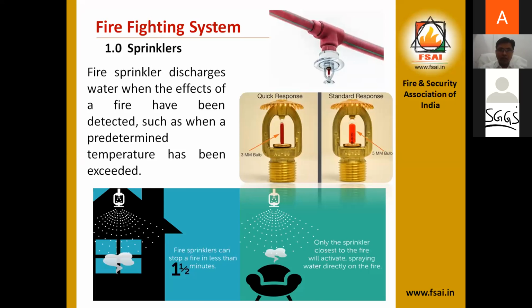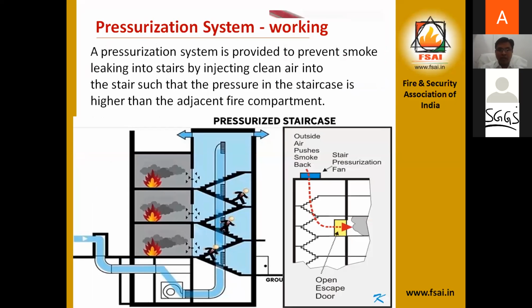The next is the pressurization system. It is a very useful system to evacuate people from the staircase areas. So we will understand what is meant by pressurization. A pressurization system is provided to prevent smoke leaking into the stairs by injecting clean air into the stair, such that the pressure in the staircase is higher than the adjacent fire compartment. You can notice in this figure, the first floor, second floor, and third floor are on fire. In spite of that, the people are coming from that compartment to the staircase and evacuating easily. Why has this happened?